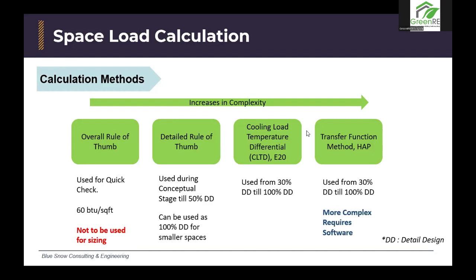It is not meant to be designed with, but again, I've seen this being used for design as well. Oftentimes, housing contractors, apartments, they'll probably use this. There's not really much losses for houses, but I have also seen it being used for office towers and whatnot. The second one is the detailed rule of thumb. It is a more detailed version. It uses some elements of detailed engineering. It uses some elements of rule of thumb, but it doesn't use the 60 BTU per square feet. I'll show you an example shortly.